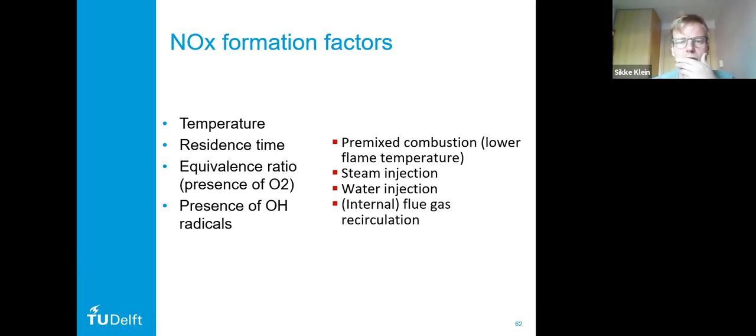Some other ways to reduce the NOx are to use either steam or water injection. So in conventional combustion, so you have non-premixed conventional combustors, you can use steam or water injection. You just inject steam or water into the flame, and therefore it has two effects. The first main effect, it decreases the temperature. And the second effect, it also changes the presence of OH radicals. So steam and water injection can be very effective to reduce NOx. The disadvantage is that it normally is not that good for the hardware. So you have a shorter lifetime of your combustion hardware.